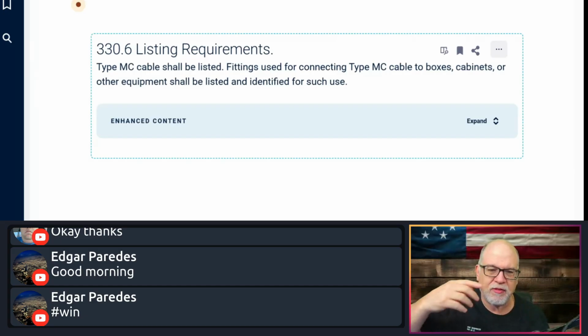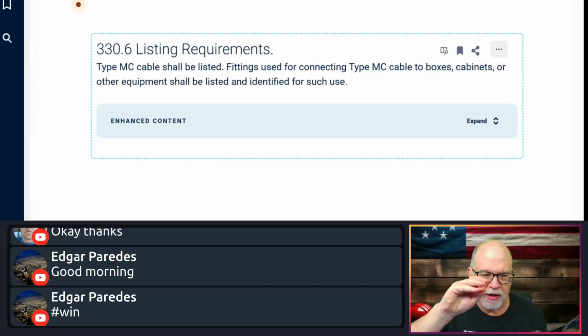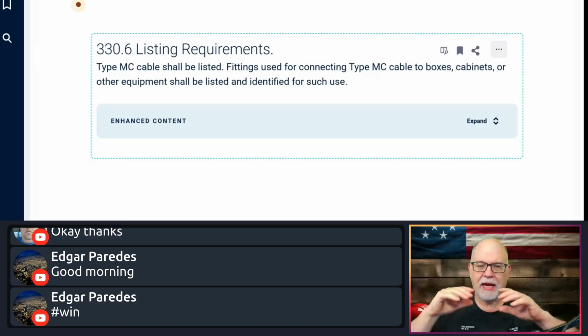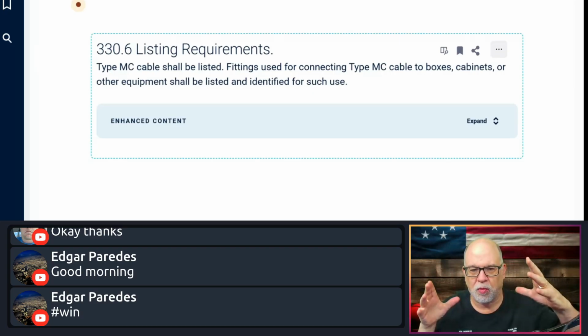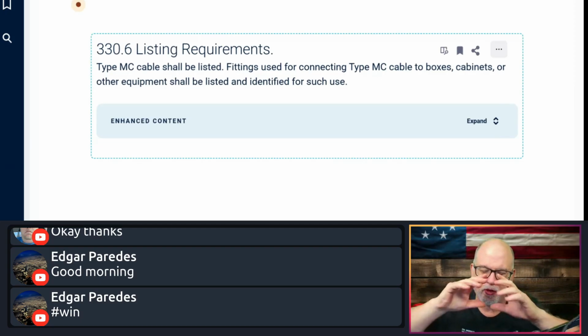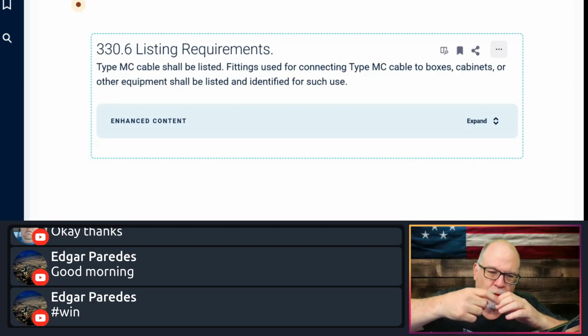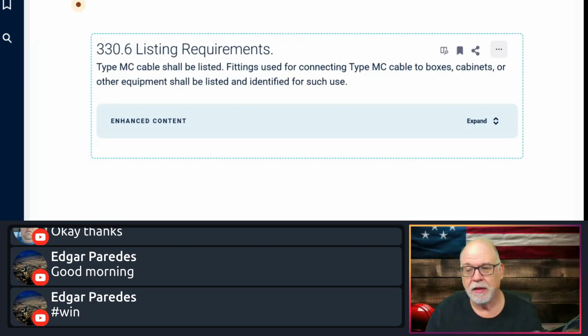So it literally makes it as the bundle of wires comes together; it actually feeds through a tunnel, and then it has this big reel of aluminum or steel wire that feeds off of it. There's a mandrel and a device with a bird's beak that bends it and forms it around the conductors, because that's interlocked. Then you also have the smooth version, which is basically an extrusion. It can be used as an equipment ground, because y'all know that interlocked cannot be used as an equipment ground on normal MC, just everyday MC that you folks use.